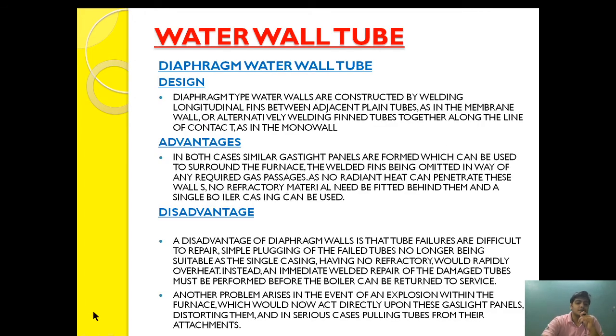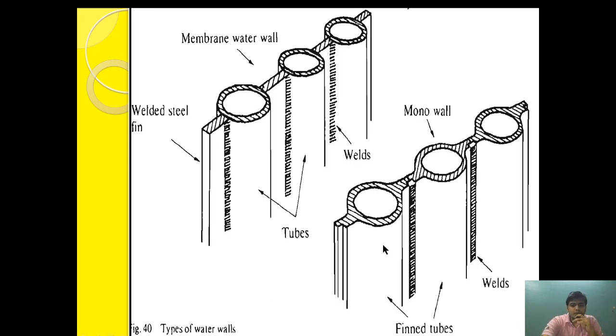A disadvantage of the diaphragm wall is that if a tube failure occurs, it is difficult to repair. Simple plugging of the failed tube is no longer suitable, since with a single casing and no refractory, it would rapidly overheat. Instead, immediate weld repair of the damaged tube must be performed before the boiler can be returned to service, as the continuous structure means any damage will cause huge leakage.